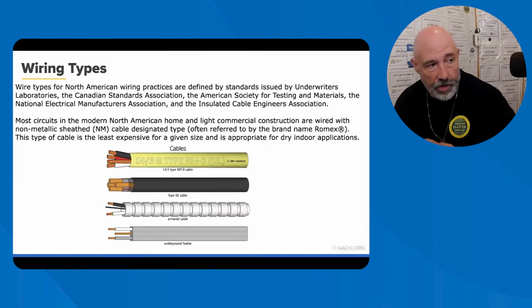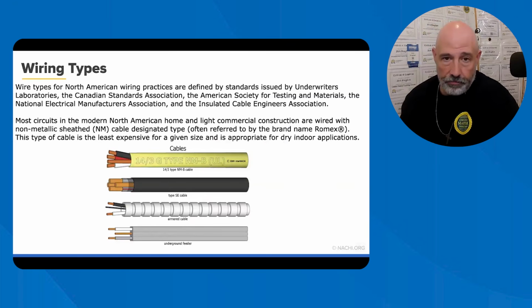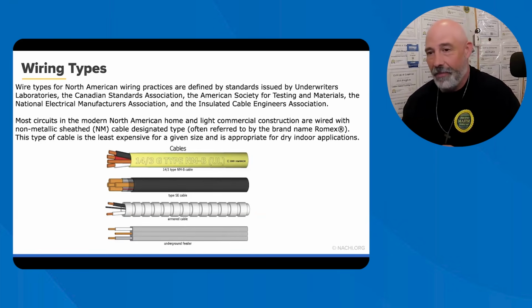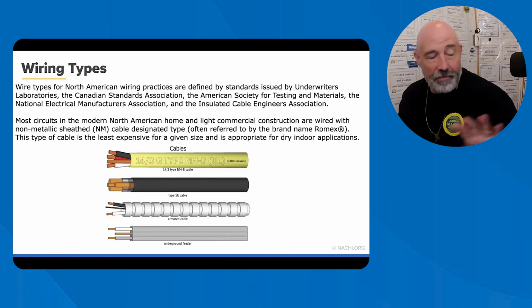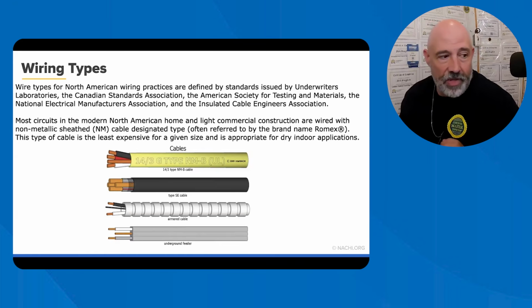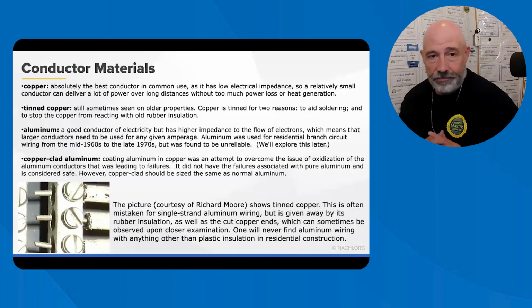So here are the common wire sizes for the non-metallic sheath cable, which is NM, commonly known by the brand name Romex. NM cable is widely used. It's more cost efficient, it's easy to install, and it's suitable for dry interior locations. Wire and cable standards in North America are established by organizations such as the UL, the CSA, the ASTM, the NEMA, and the ICEA. Totally useless knowledge. You don't even know that, but it's good to know what you're looking at here. So the underground feeder, the armored cable, the SE cable, and of course the Romex or the other cable.